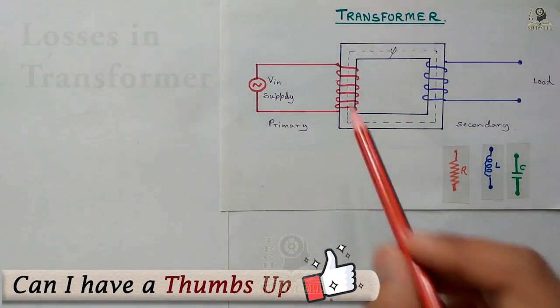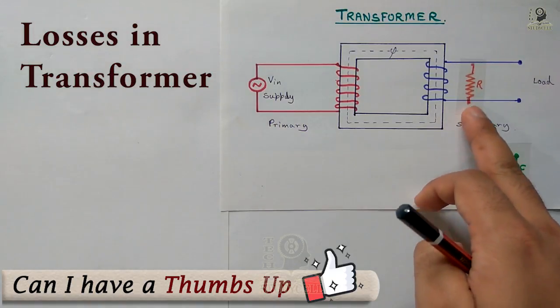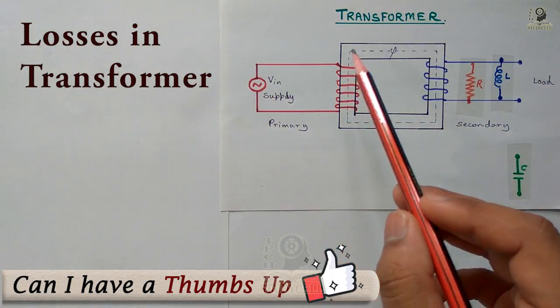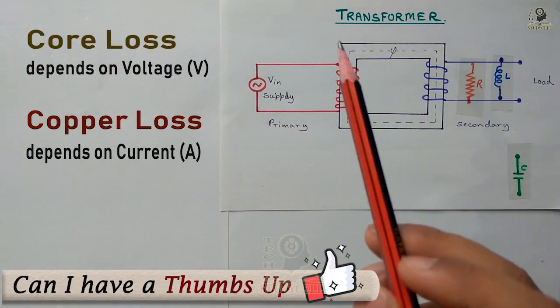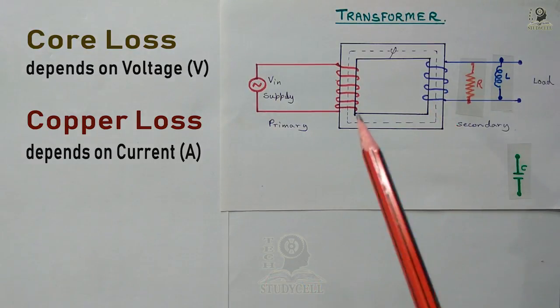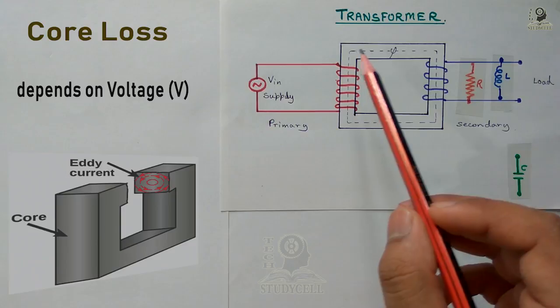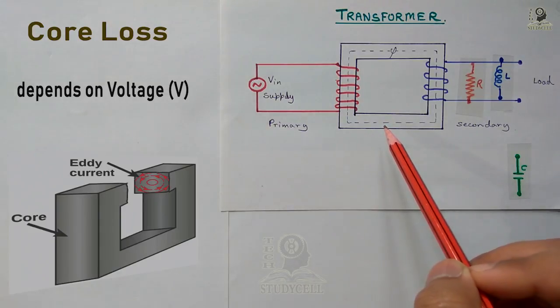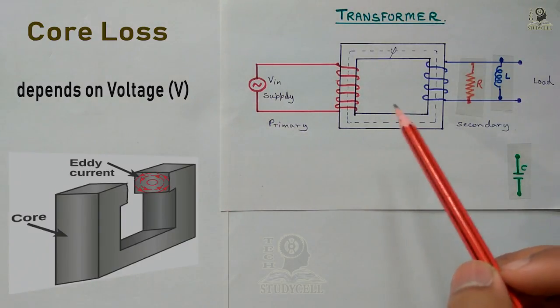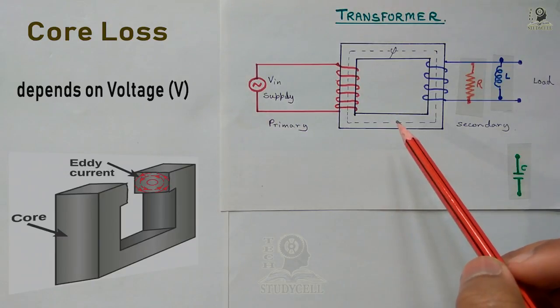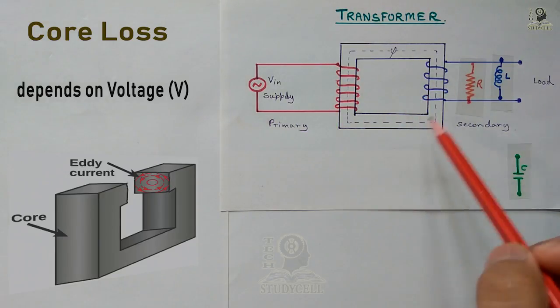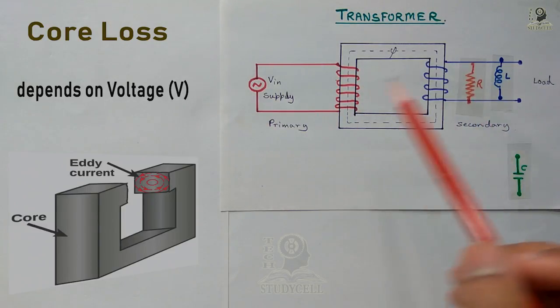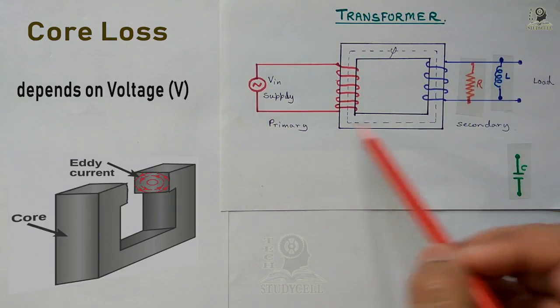The next reason is the losses that occur in the transformer. If there is a resistive and inductive load at the secondary, then there are two types of losses in the transformer: core loss and copper loss. The core loss or iron loss depends on the voltage of the transformer and the magnetic property of the core material. As the magnetic property of a core material is constant for a transformer, the core loss depends on the voltage. During operation, the input and output voltage of a transformer remain constant, so core loss is a constant loss.